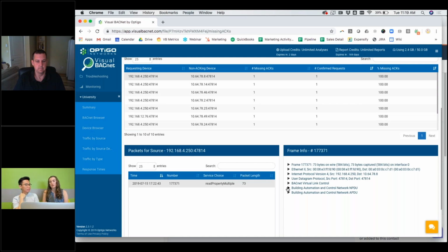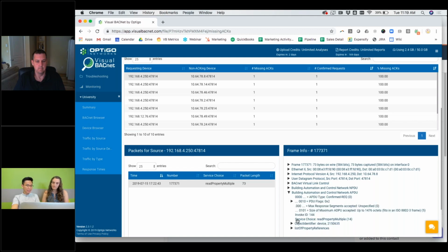For a read property multiple, the acknowledgement would include the data. So my suspicion, since the network is filled with mostly who has requests, is that it might have been congested for the response to come back, or even for the request to reach. Yeah, that's my initial guess.